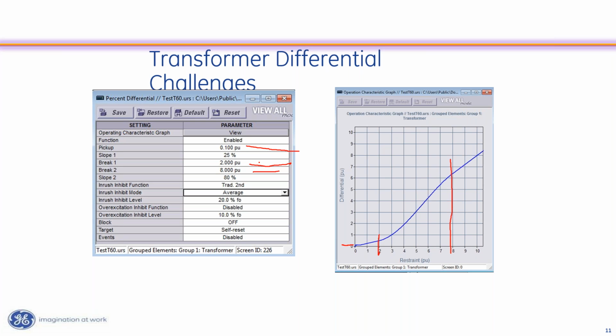Now, below breakpoint 1, we use the low slope setting. And above breakpoint 2, we use the high slope setting. Now, what those slope settings basically say is how much of the differential you need to have, of the restraint, to operate. So below breakpoint 1, with these settings, if my differential is 25% of my restraint, I'd operate, right? So that means if I had 1 per unit of restraint, if my differential was 0.25 per unit, I'd operate.